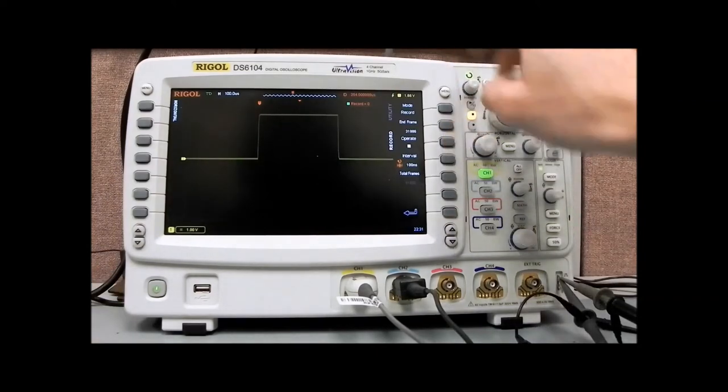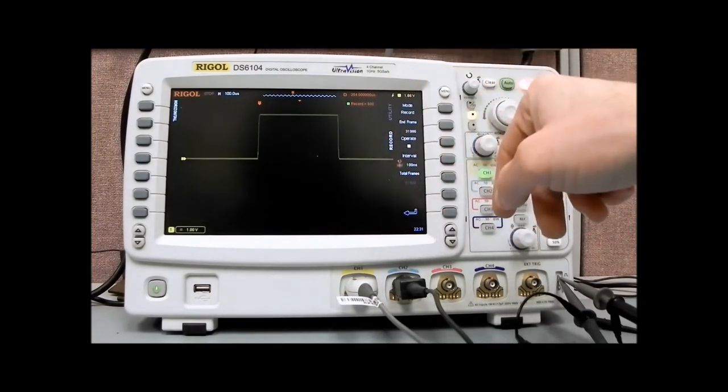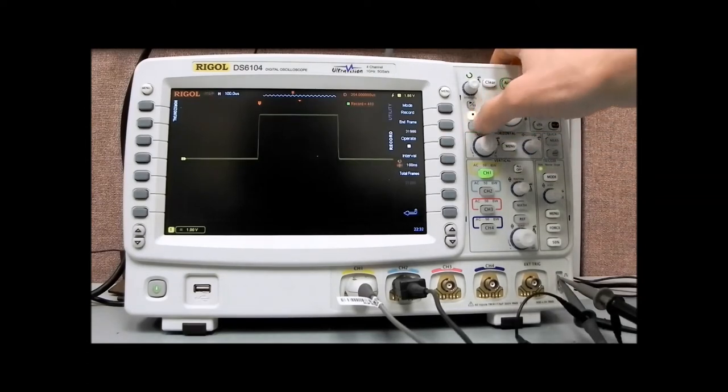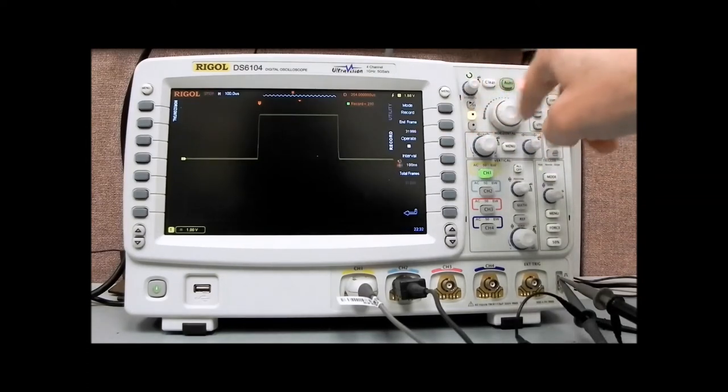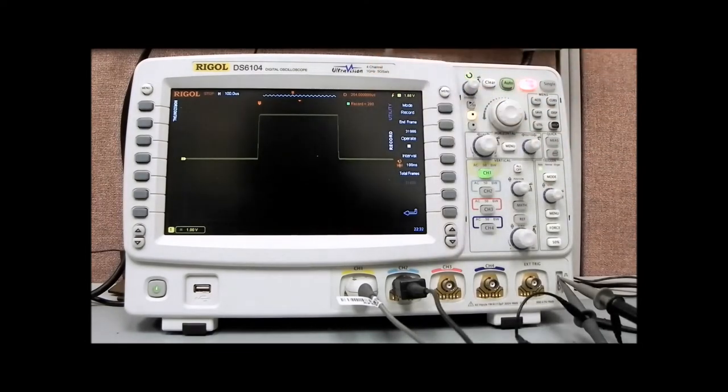To record, very straightforward, we can press the operate key here and you'll see we'll start to collect. We can stop it, or even better, we can use the record/stop buttons in this ultra-vision area. You see we've collected 280 waveform recordings, and now we can actually analyze that data.